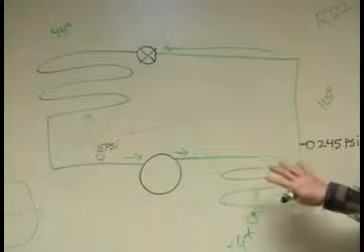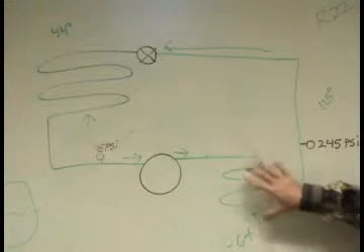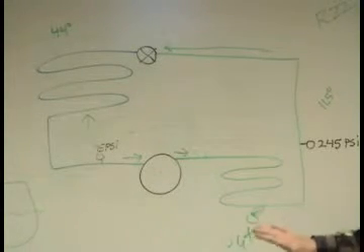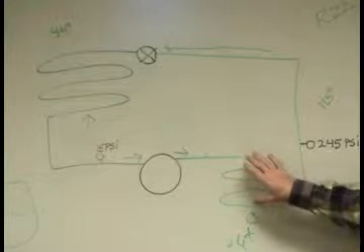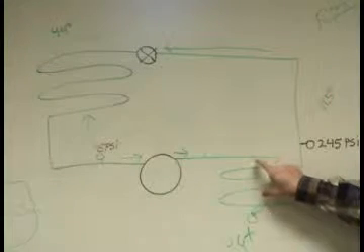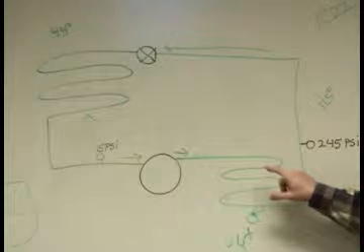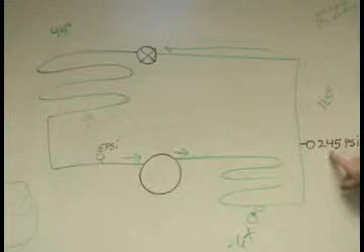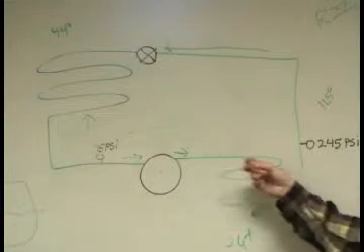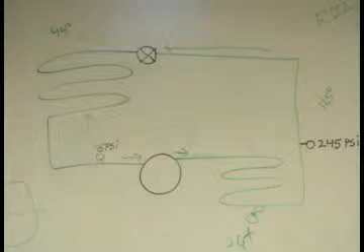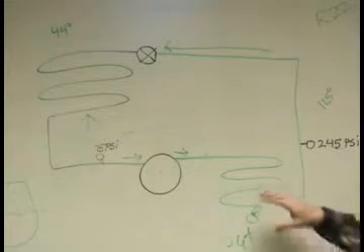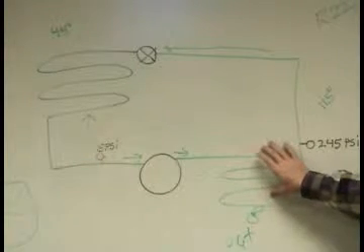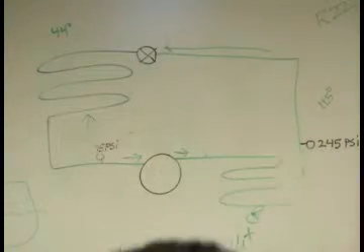What happens when all the cottonwood in the neighborhood sucks into this coil here? Efficiency goes down a little bit. Efficiency goes down terribly. Our pressure probably goes up. We can't get rid of the heat. How do you keep it out of there?